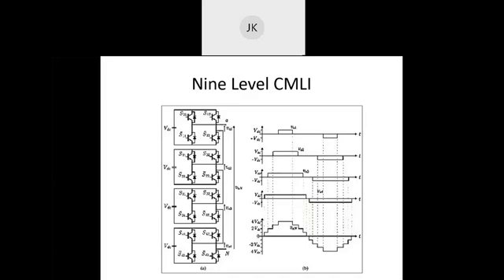Now what should be this width for H1 bridge, H2 bridge, H3 bridge, H4 bridge? I will discuss this separately in the switching scheme slides. If we choose properly these angles or widths of the positive and negative pulses, we can reduce THD also. Otherwise, for random width there will be different THD. If we increase or decrease, the requirement is that, as seen in the last waveform, it should be nearer to sinusoidal. So we have to ensure that.